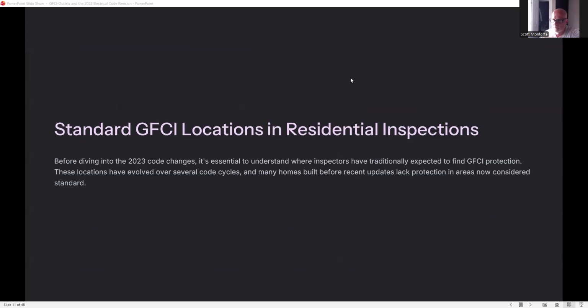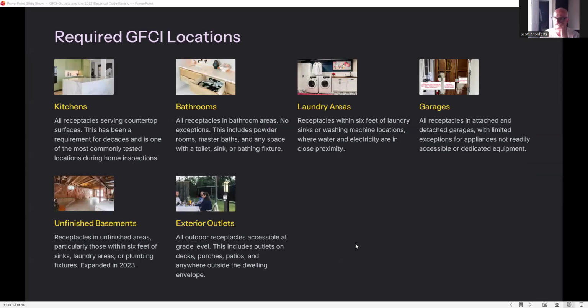Standard GFCI locations in residential inspections. Before diving into the 2023 code changes, it's essential to understand where inspectors have traditionally expected to find GFCI protection. These locations have evolved over several code cycles, and many homes built before recent code updates lack protection in areas now considered standard. Kitchens, bathrooms, laundry areas, garages, unfinished basements, and exteriors. So when we're in the kitchen, all receptacles serving countertop surfaces. This has been a requirement for decades and is one of the most commonly tested locations during a home inspection. Bathrooms, all receptacles in bathroom areas, no exceptions. This includes powder rooms, master baths, and any space with a toilet, sink, or bathing fixture.